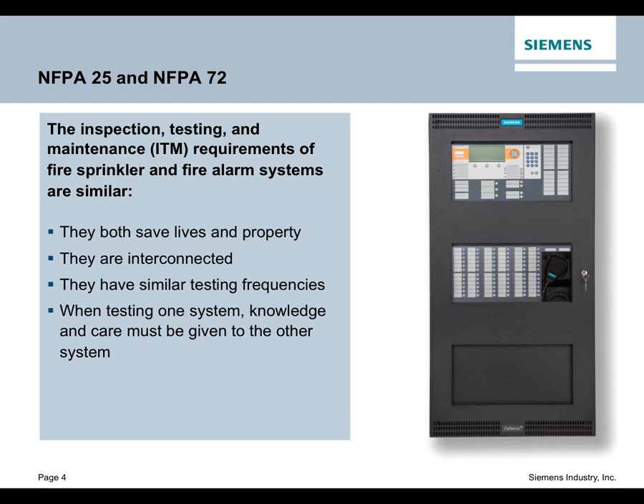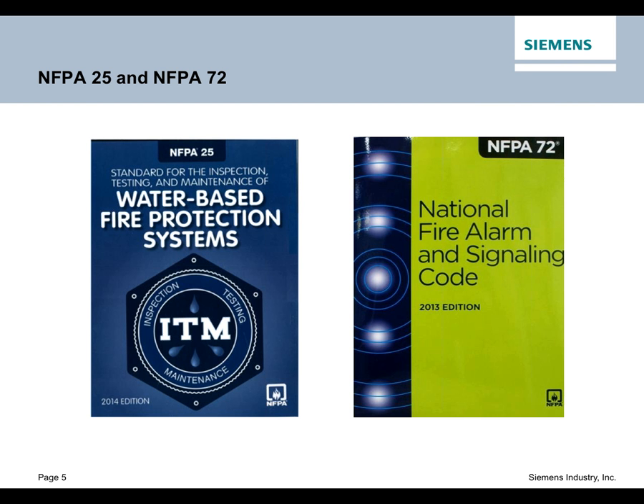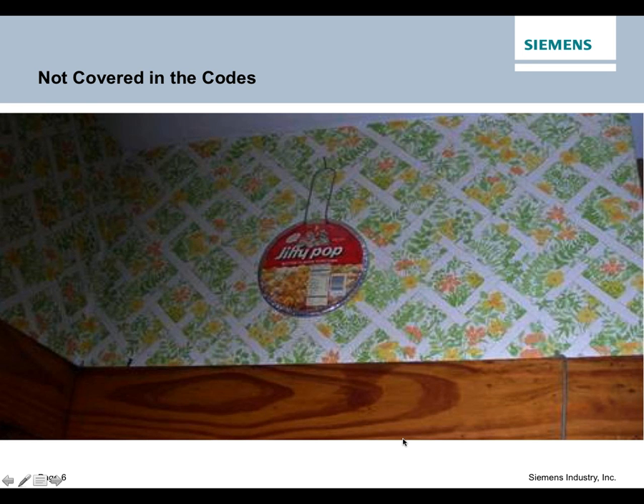So as I mentioned before, the two codes on your screen, NFPA 25 and NFPA 72, are the key documents. NFPA 25, water-based fire protection systems, is the fire sprinkler system standard. And next to it is NFPA 72, which is, of course, the document on the National Fire Alarm and Signaling Code. It's interesting to note, too, that years ago NFPA 72 was known as just the National Fire Alarm Code, but just recently they've changed that to include signaling, because in today's world, signaling is just as important as detection. By signaling, of course, we mean the notification and the communication that takes place.